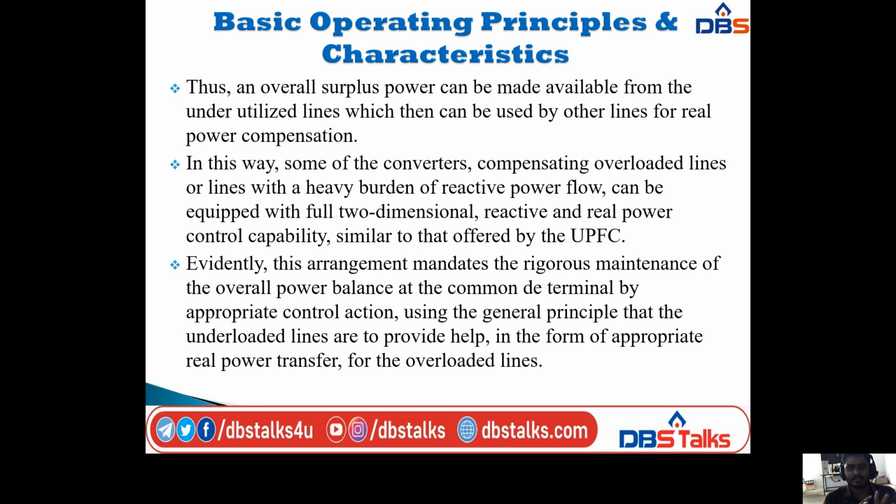In this way, some of the converters compensating overloaded lines, or lines with a heavy burden of reactive power flow, can be equipped with full two-dimensional reactive and real power control capability, similar to that offered by UPFC.